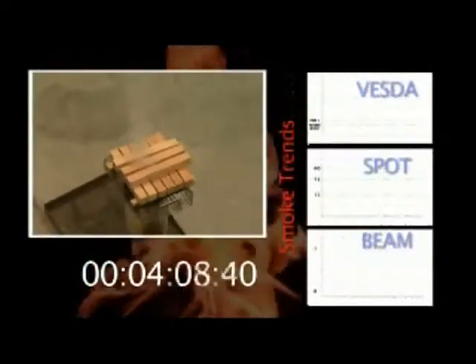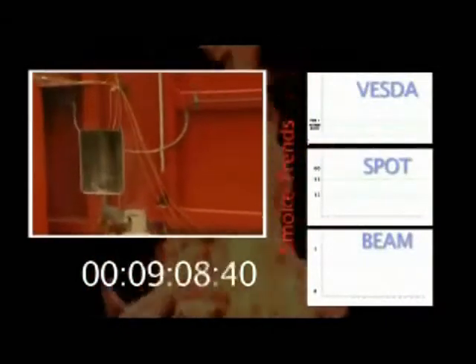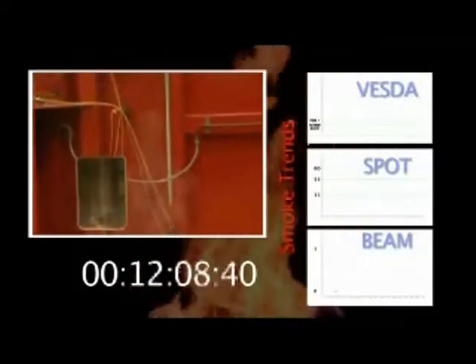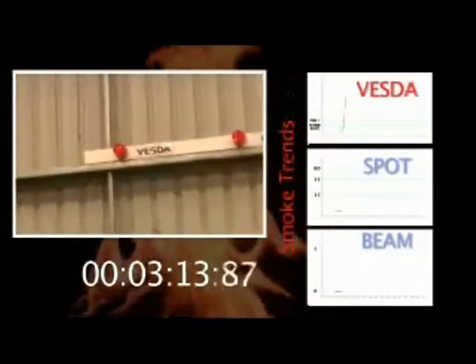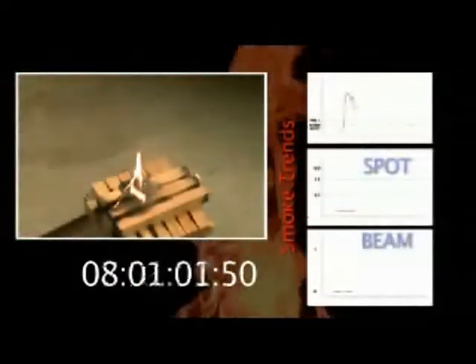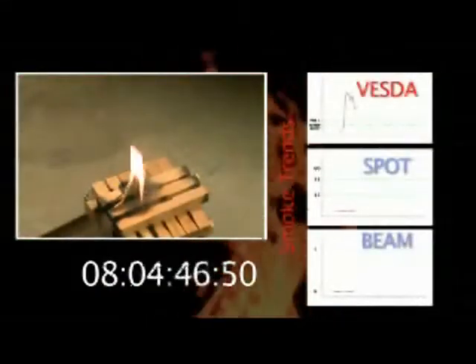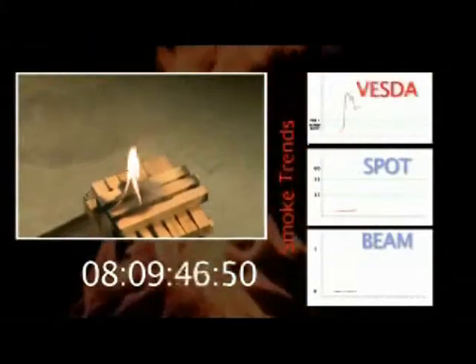The burning wood initially undergoes smouldering combustion, generating white smoke, followed by flaming combustion with little visible smoke present. At three minutes, the VESDA detector has gone into alert, and at three minutes twelve seconds, into fire alarm one. Meanwhile, as you can see, the fire is still very small and manageable. Eight minutes into the fire, neither the point nor beam detector have picked up the smoke — a clear win to the VESDA system.